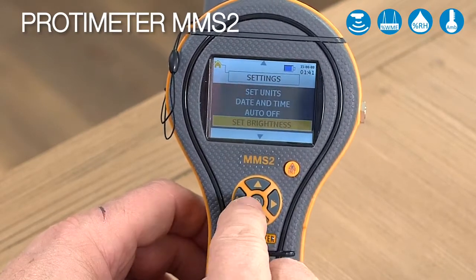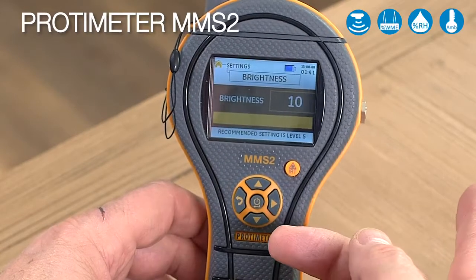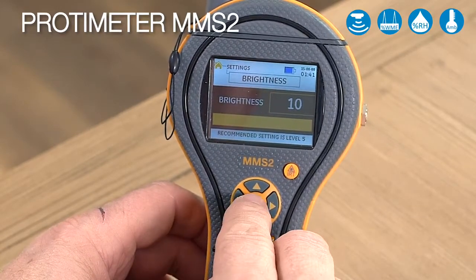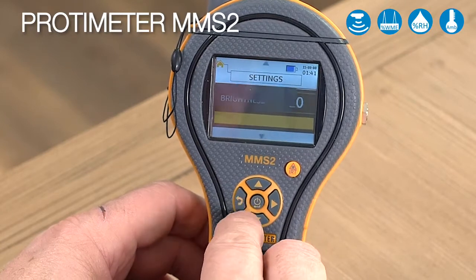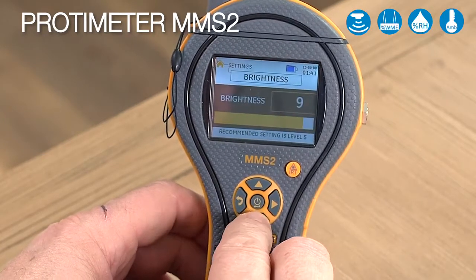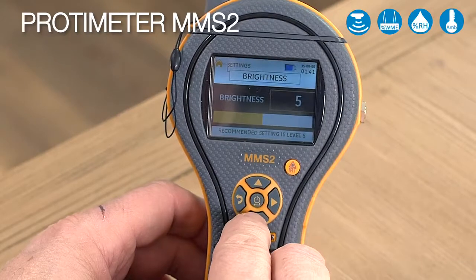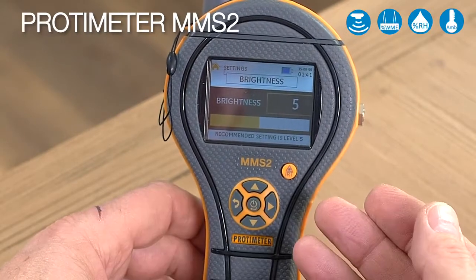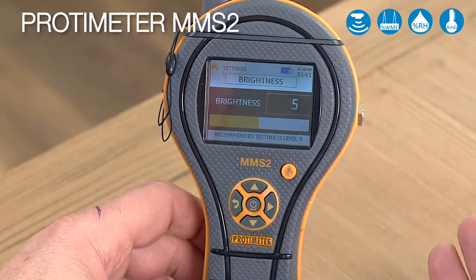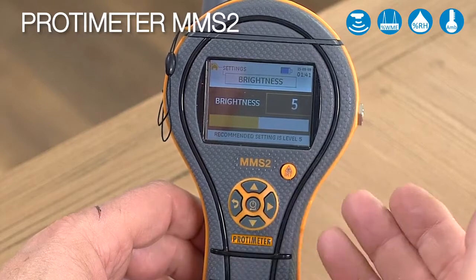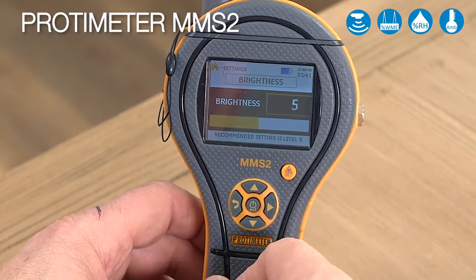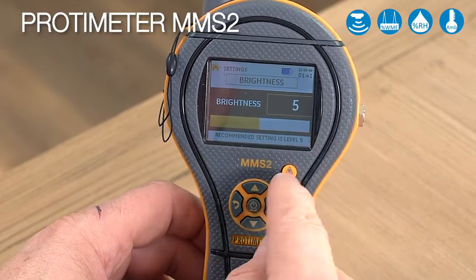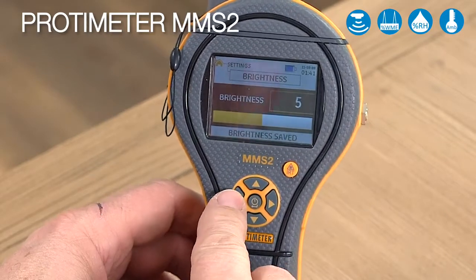Back to the main menu, we'll set our brightness. It's currently set at 10 - if we want to change that we use the arrow buttons to select the appropriate setting. If you leave it at 10 you'll use the battery up quicker than at 5, so set it to what's appropriate to maximize battery time. We'll set ours to 5, hit enter, and it's now at 5.